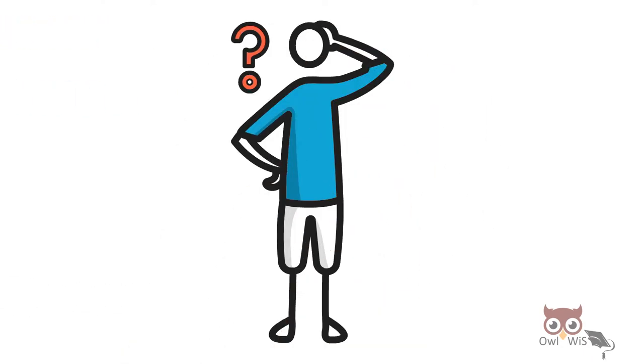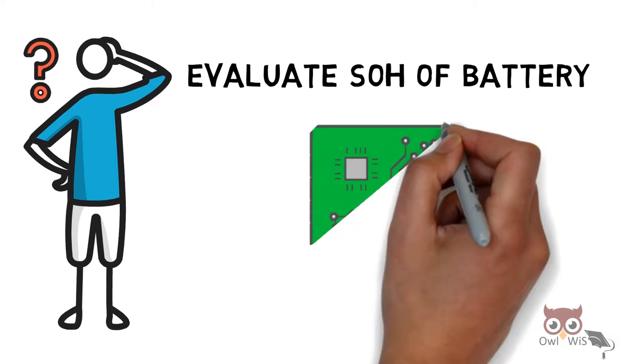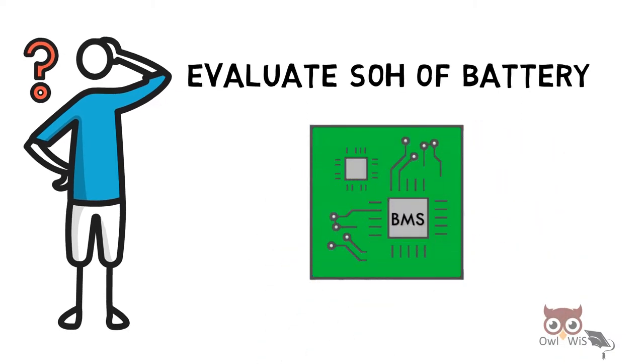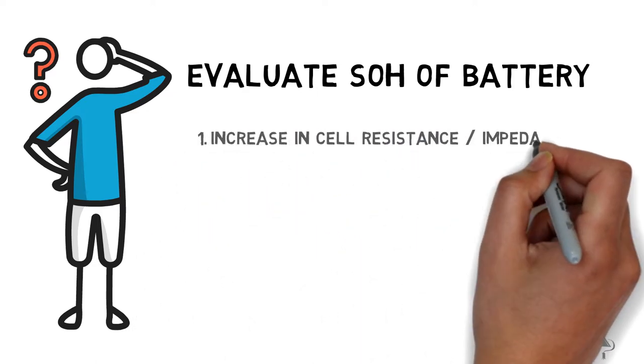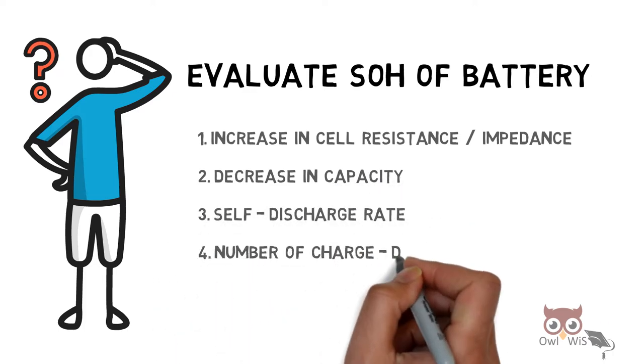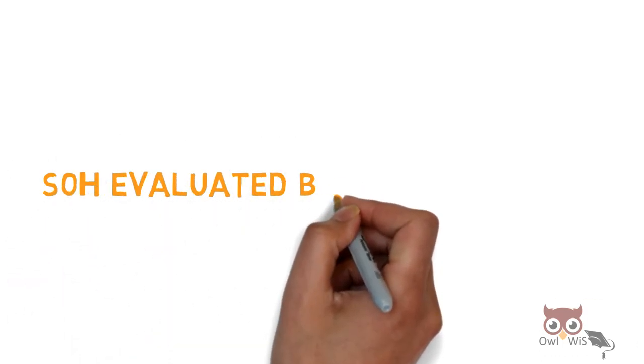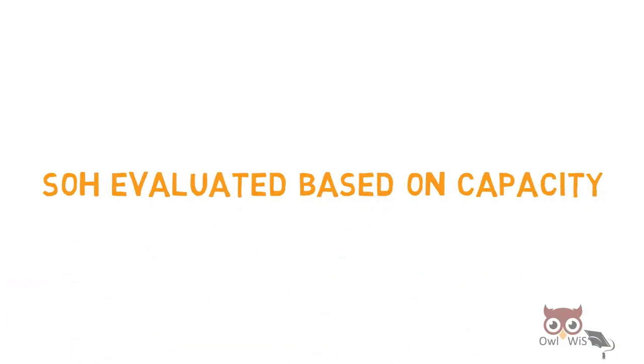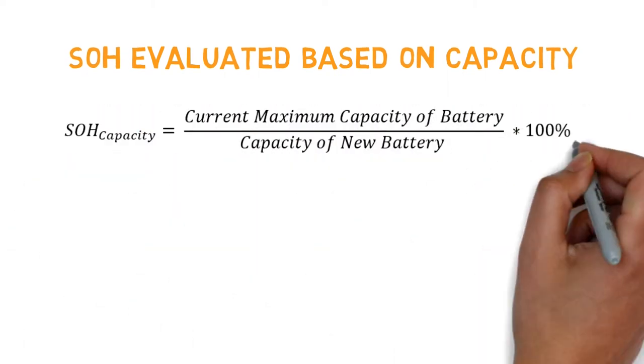The BMS uses a combination of parameters to evaluate SOH, such as increase in cell resistance or impedance, decrease in capacity, self-discharge rate, number of charge-discharge cycles, and age of the battery.